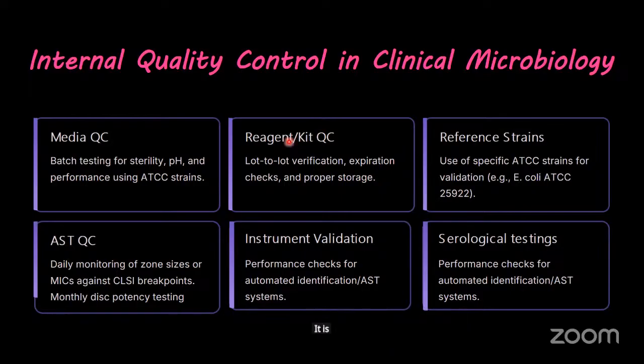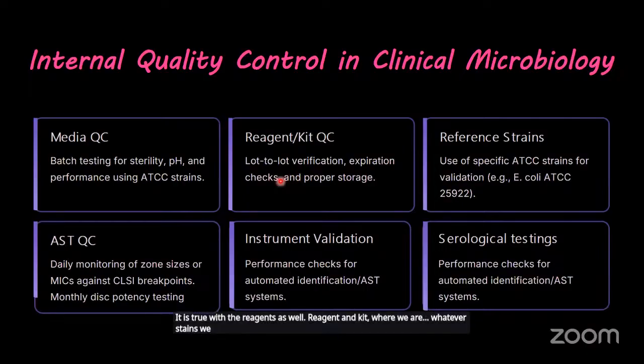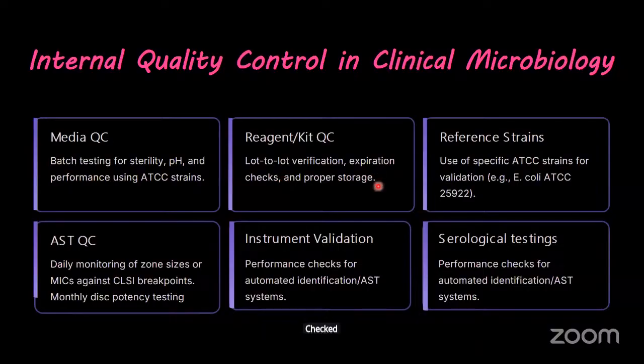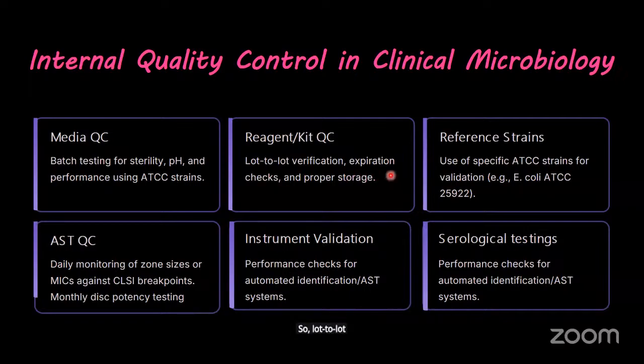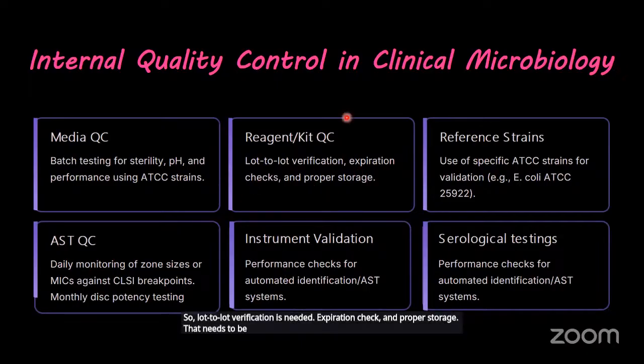It is true with the reagents as well, reagents and kits, and whatever stains we are using, that must be checked frequently to see whether they are giving the result properly or not. And the reagents must be validated from lot to lot. So lot to lot verification is needed, expiration check and proper storage need to be done, and quality control records should be maintained.